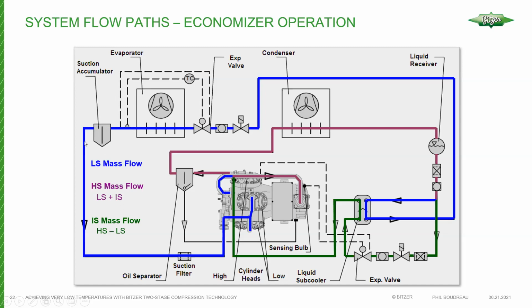Keep in mind, these are direct suction compressors, so you want to make sure you've got good, stable, sufficient superheat, and also a good idea to have a trap for those transients where you may have a little bit of liquid traveling down that pipe. And in a well set up system with proper defrost and everything else, you should never see this, but sometimes this will be the case. Then the suction gas travels back to the two heads that I mentioned through that suction manifold on the compressor. And then we start the process all over again.